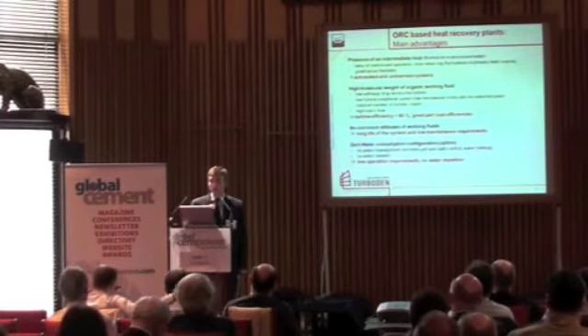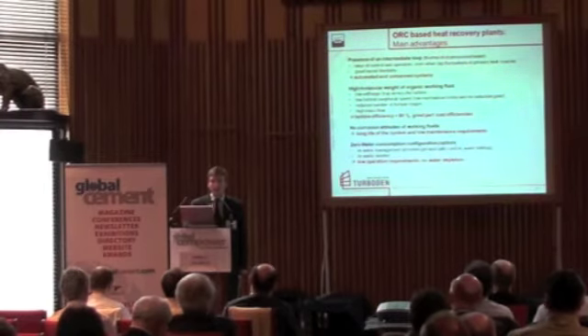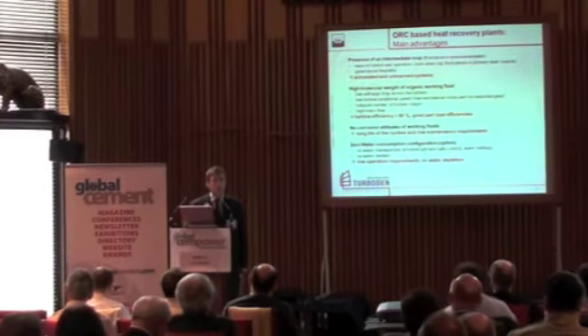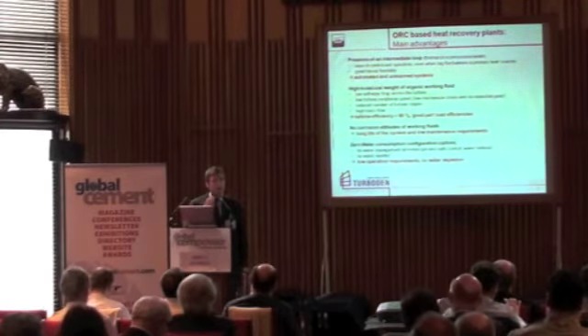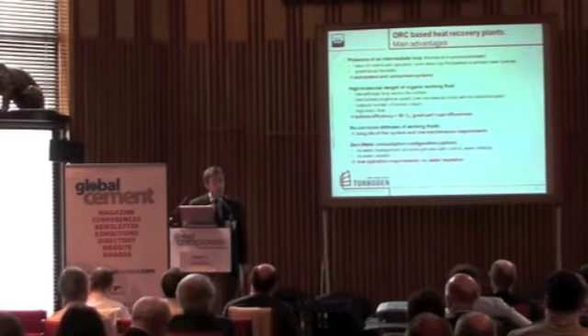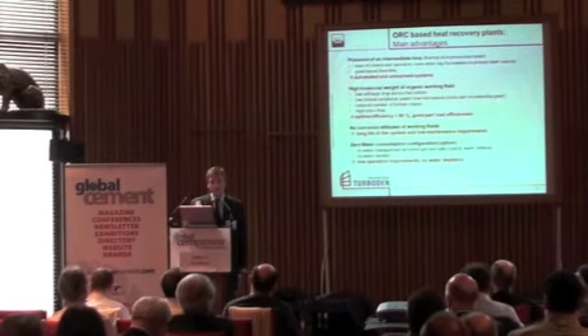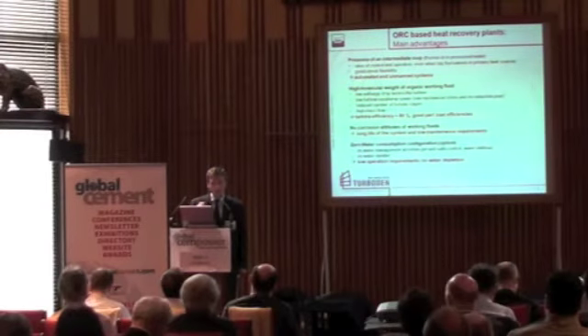For a given electric output, a low enthalpy drop also means a high mass flow, which brings advantages in designing the turbine. Maybe most of you are not familiar with turbine design, but you must imagine that managing a bigger flow makes designing a turbine a much easier job, because the blades are bigger and the sealing losses between blades and casing influence the overall turbine efficiency less. So just to summarize these technical points, I'm definitely open to talk about these details after the presentation.